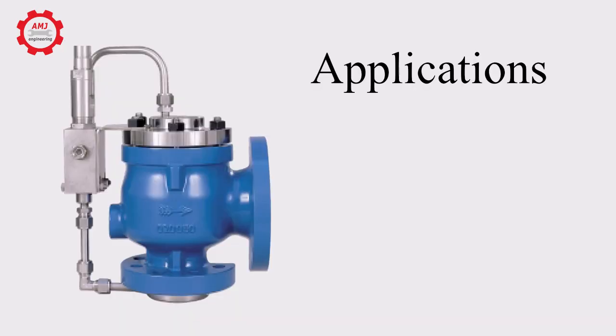These valves are best suited for high pressure, high volume applications. Although their operation is slower than that of direct acting relief valves, pilot operated relief valves maintain a system at a more constant pressure while relieving.